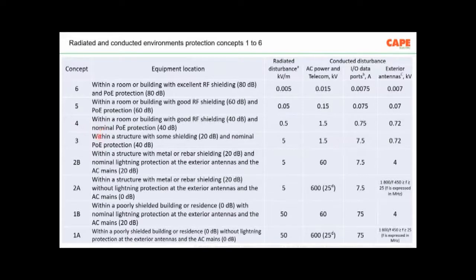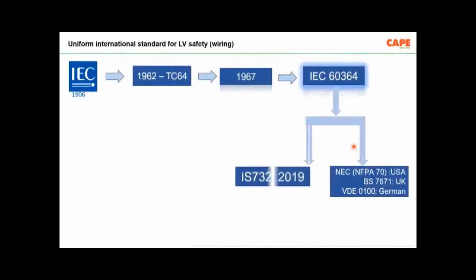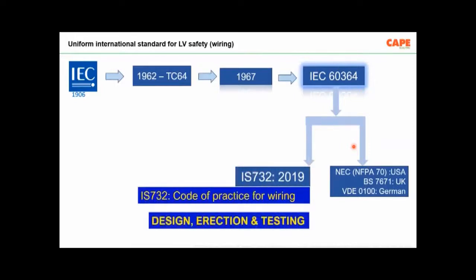So with the concept 3, for example, the radiated disturbances inside the building, it still goes up to 5 kV, and these are the limits which is produced. Now, what I am trying to explain to you is, if you look at any of the international standards with the EMI, EMC, the foreign standards like American standards or British standard or whatever, what they say is the basic electrical system shall satisfy the national wiring rule. That is regarding the safety.